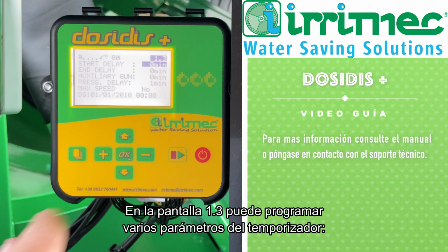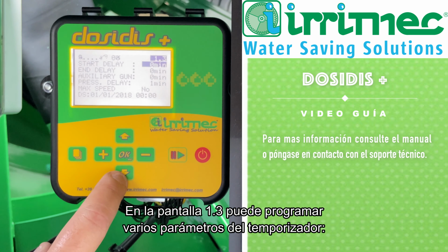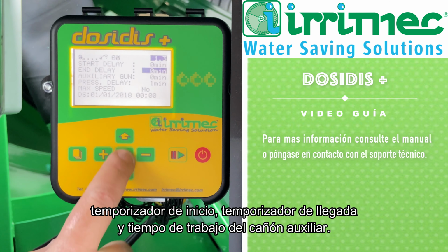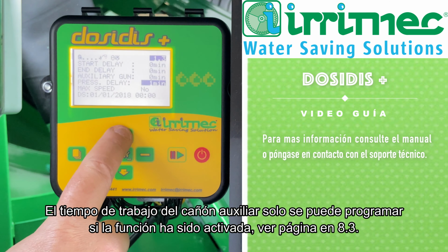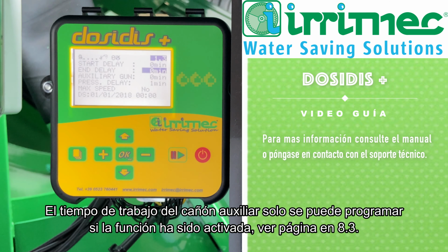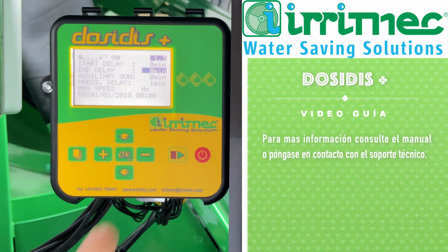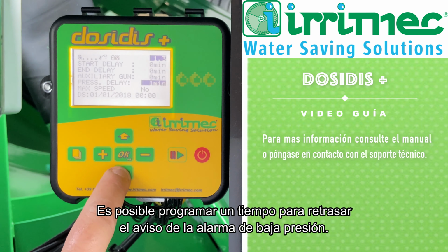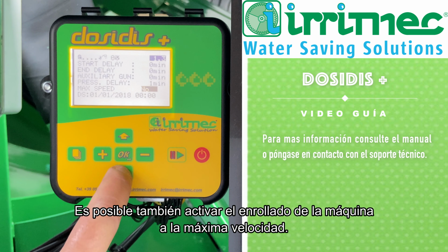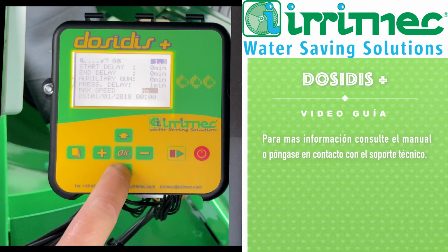In screen 1.3, you can program various time-based parameters: start delay, end delay, and auxiliary gun working time. Auxiliary gun time can be programmed only if the function has been activated in 8.3. On press delay, you can program a time to retard the intervention of the pressure alarm. You have also the function to wind up the machine at max speed.